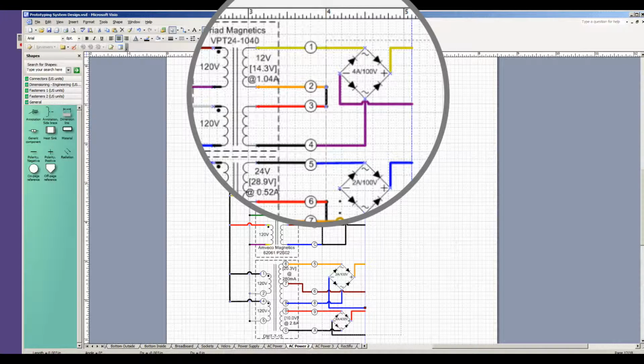So I use a derating factor of 1.25 to get higher than the specs that I need. So, taking my 33.9, I'm going to multiply that by 1.25, and I get 42.4 volts. That represents the minimum volts that my diode bridges and capacitors need to be able to deal with. Now, the bridges that I'm going to be using here for this particular secondary can handle 100 volts, which is fine. The capacitor can handle 50 volts, which is also fine. Now take a look at the current. My specification for the current coming out of this first secondary was 500 milliamps. I didn't think I would need any more than that.